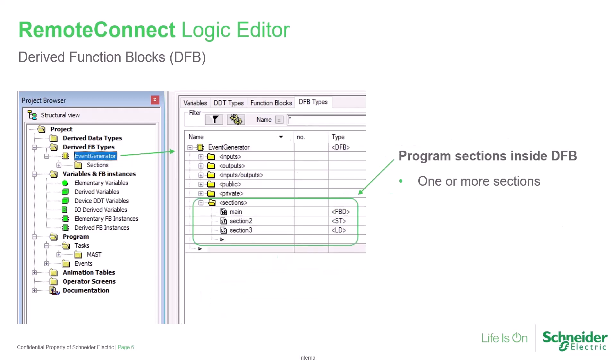A derived function block may be built with one or more logic sections, allowing functionally different logic to be kept separate. Each section may be developed with any of structured text, function block, ladder diagram, or instruction list, whichever is most suitable.